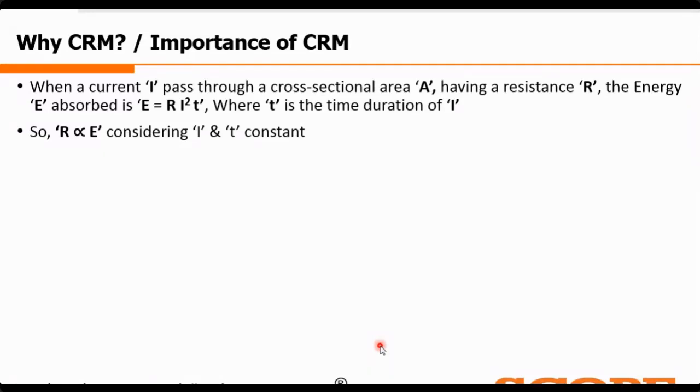So it is more of a cascading effect. Once the heating effect starts, this cascading effect starts, and because of that the contact resistance gradually becomes high. And because of that, when you do the contact resistance measurement test, you will see that the R value is coming quite high.